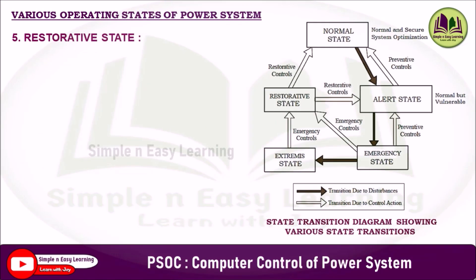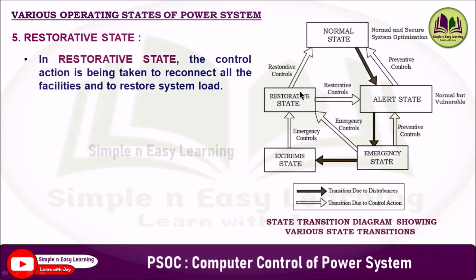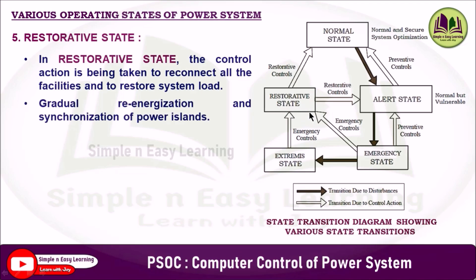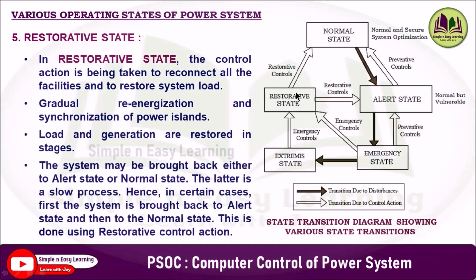In the restorative state, control actions are taken to reconnect all facilities and restore system load through gradual re-energization and synchronization of power islands. Load and generation are restored in stages. The system may be brought back to either the alert state or the normal state. Since going directly to the normal state is a slow process, in certain cases the system is first brought back to the alert state and then to the normal state.